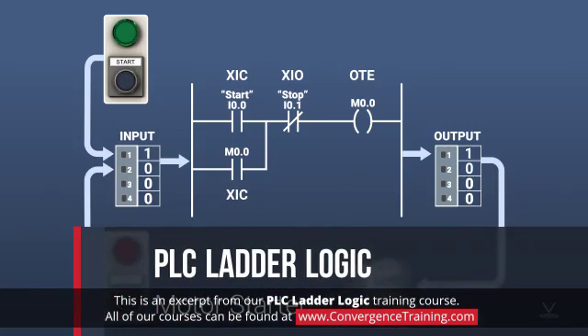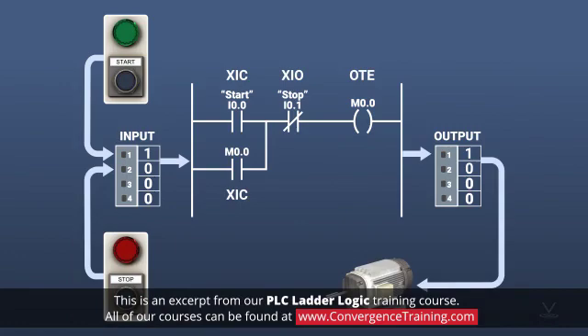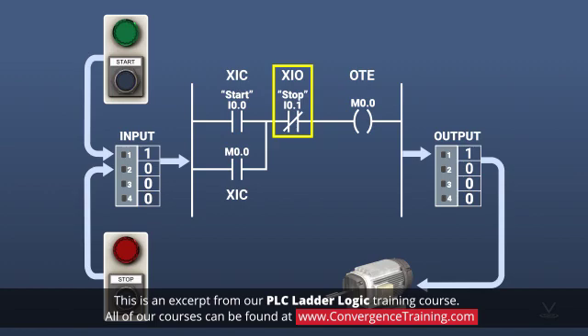The use of these common ladder logic instructions is illustrated in a typical push-button based motor starter circuit. In this diagram, each instruction is associated with a memory address that is connected to a physical device. XIC in 1 represents a normally open momentary contact start switch. XIO in 2 represents a normally open momentary stop switch. OTE out 1 represents a relay coil that starts a motor.